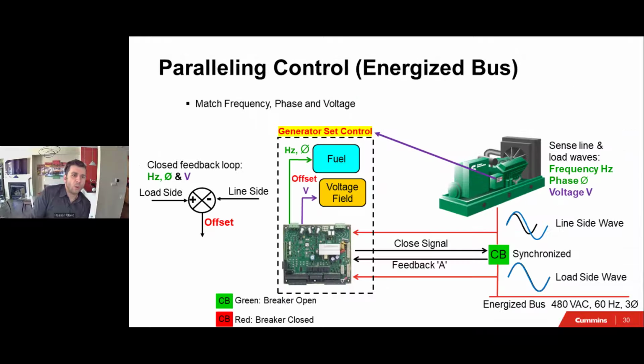Okay, so with paralleling control, the way it works, I'm just going to give you a little bit more information on it. On this system, I have a generator that's right now up and running. The circuit breaker is open, and let's say the bus is already energized and it's at 480. So here's my generator set controller, the one that I just showed you. And as you can see, it's my attempt to show you that the two waveforms are not synchronized. So you can see that this is a little bit out of sync, the line side and the load side. Before we close, the circuit breaker is open. We need to match phase, voltage, and frequency.